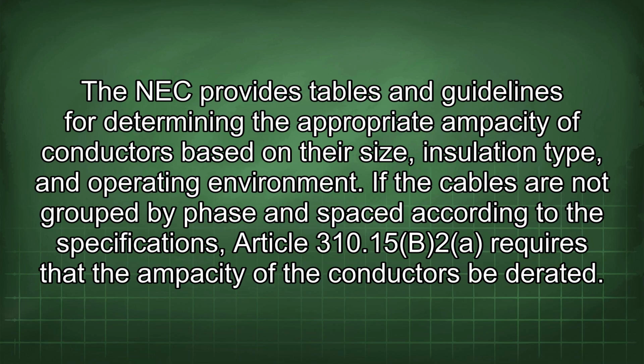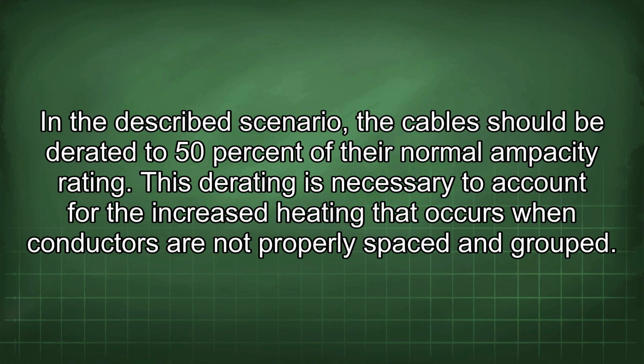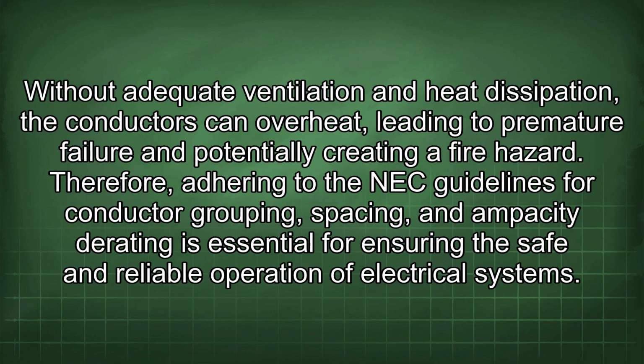The NEC provides tables and guidelines for determining the appropriate ampacity of conductors based on their size, insulation type, and operating environment. If the cables are not grouped by phase and spaced according to the specifications, Article 310.15b2 requires that the ampacity of the conductors be derated. In the described scenario, the cable should be derated to 50% of their normal ampacity rating. This derating is necessary to account for the increased heating that occurs when conductors are not properly spaced and grouped. Without adequate ventilation and heat dissipation, the conductors can overheat, leading to premature failure and potentially creating a fire hazard. Therefore, adhering to the NEC guidelines for conductor grouping, spacing, and ampacity derating is essential for ensuring the safe and reliable operation of electrical systems.